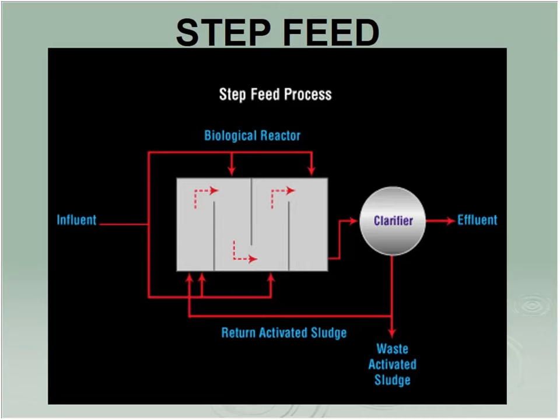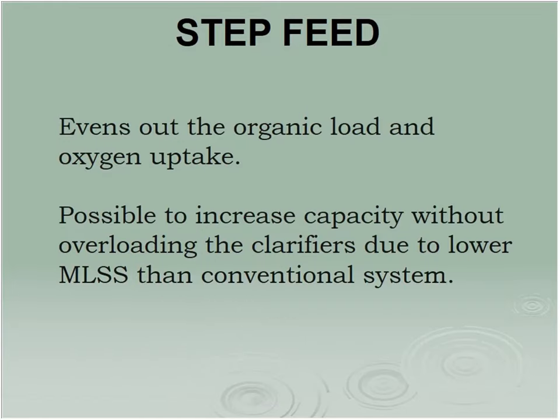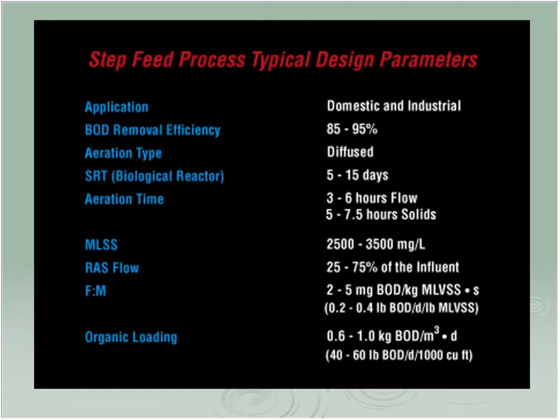Step feed. Step feed is a combination of complete mix and plug flow. You've got a complete mix setup, but by redistributing your feeds all the way around, you get something very close to a complete mix. And what you've got in this is a very steady oxygen supply all the way through the reactor. Unlike with the plug flow, we had a very high demand up front and very little out the back. It evens things out, keeps a nice steady oxygen demand all the way through. Again, you look at the numbers, they'll all do pretty much the same type of job for you.